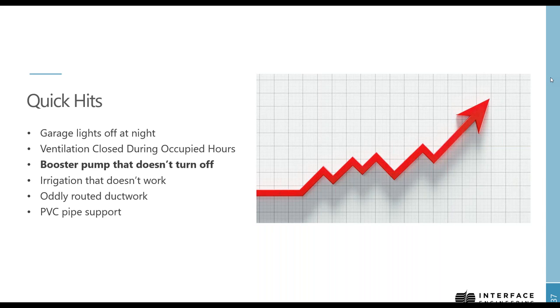Additionally, under this situation, the pump was running so often and deadheading, since there was no flow in the system, that our domestic cold water was now upwards of almost 90 degrees in some instances, just because of the heat that was being produced by this pump running and running and running when there is no flow.